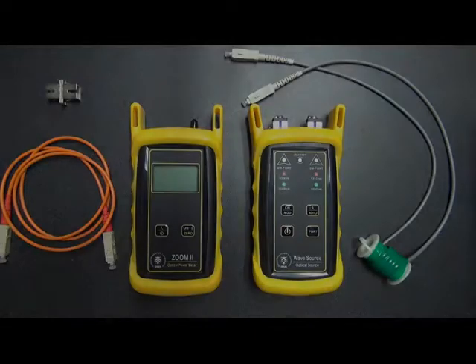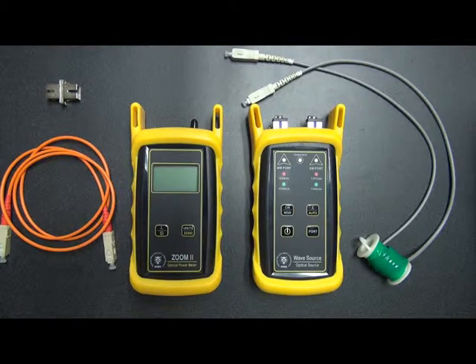This video will help demonstrate how to check your Zoom 2 optical power meter for proper operation using a WaveSource multimode light source. Patch cables and test equipment should always be checked prior to testing to ensure accurate and reliable test results. Usually a good time to do this is at the beginning of every testing day.